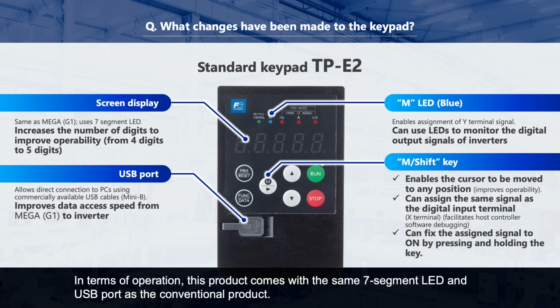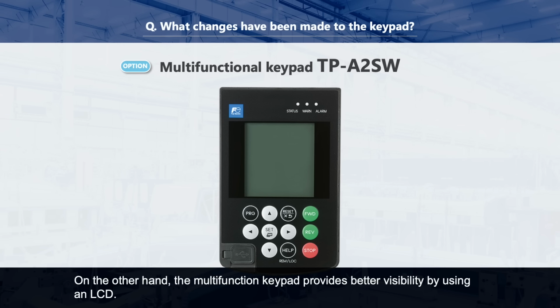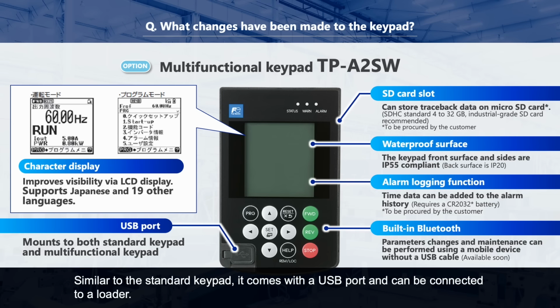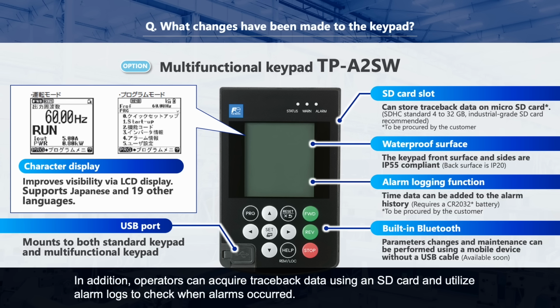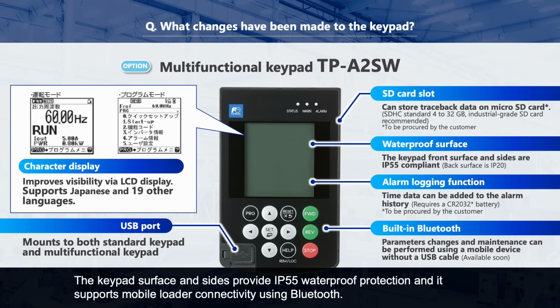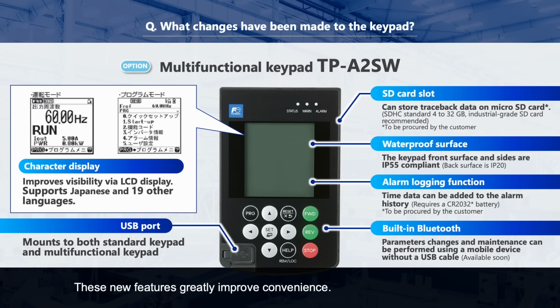In terms of operation, this product comes with the same 7-segment LED and USB port as the conventional product. On the other hand, the multifunction keypad provides better visibility by using an LCD. Similar to the standard keypad, it comes with a USB port and can be connected to a loader. In addition, operators can acquire traceback data using an SD card and utilize alarm logs to check when alarms occurred. The keypad surface and sides provide IP55 waterproof protection, and it supports mobile loader connectivity using Bluetooth. These new features greatly improve convenience.